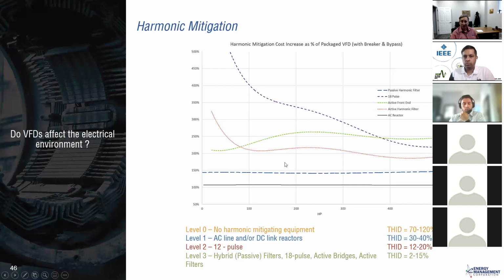Now again, you get the right application and the active harmonic filter can become very, very cost effective. This compares with your active front end, which is processing all of that power, and you also generate maybe a little bit more EMI and RFI if you don't have good filtering, so the filtering costs you more money. We look at a couple of levels. Zero would be no harmonic mitigating equipment. You're going to see 70 to 120%, depending on your source impedance. With AC and DC link reactors, 30 to 40%. That's a very cheap way to start. 12 pulse, some have gone to that. Theoretically you can get to 12%, but with any voltage imbalance you're right back up there.